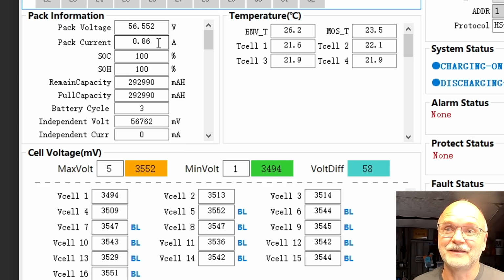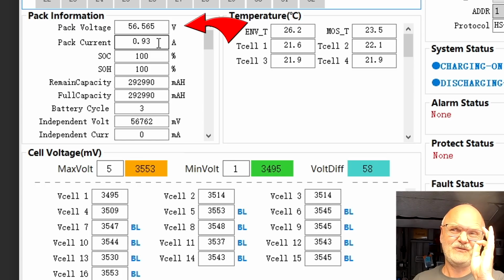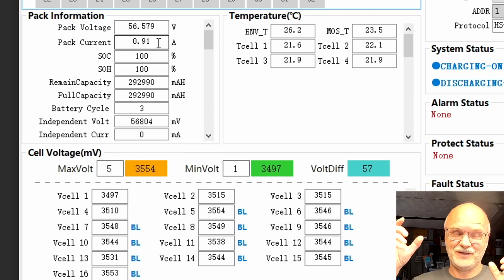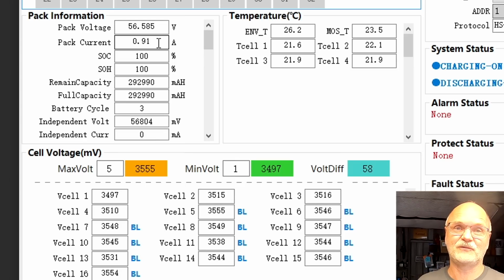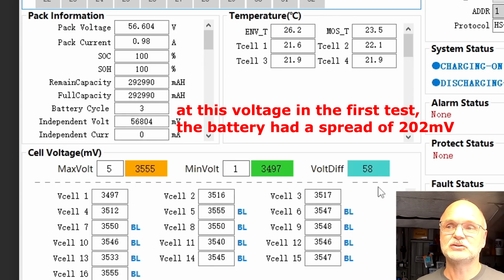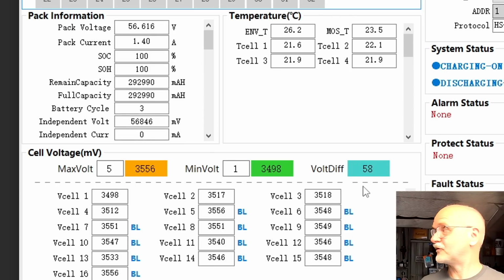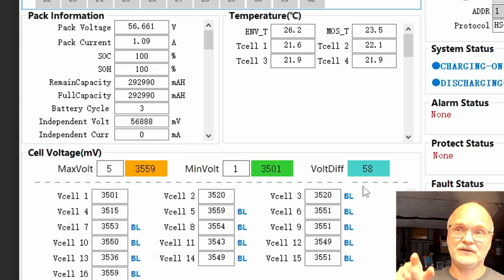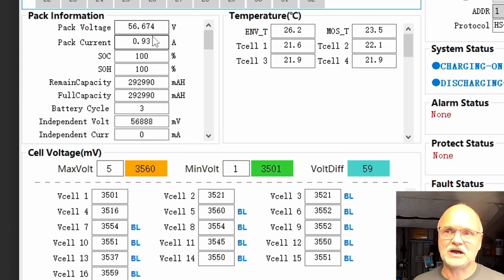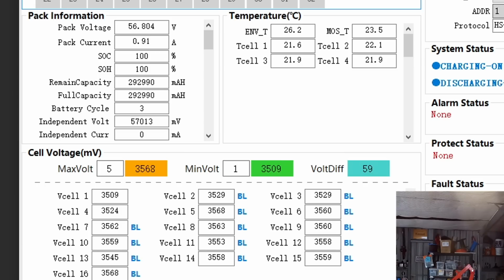We are charging only with 860 milliamps at the moment, but we are at 56.5 volts. This is almost the same voltage as in the first test with the active balancer active, when we reached 3.65 volts. And here we can already see we are at 3.55 only, and I have a deviation of 58 millivolts. So it seems like, oh, the sun is coming back. So it seems like now this pack is better balanced. Doesn't matter, as long as we charge and the voltage increases, I'm fine. We just need to wait until one cell hits 3.65 volts, read the voltage and deviation, and then we can compare. No, it's not going to happen.